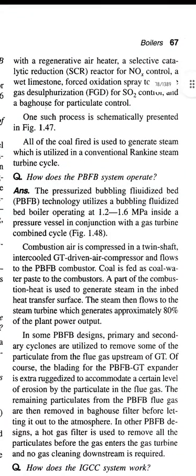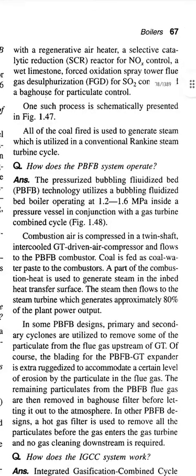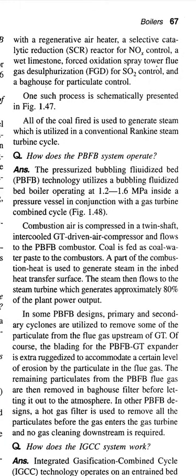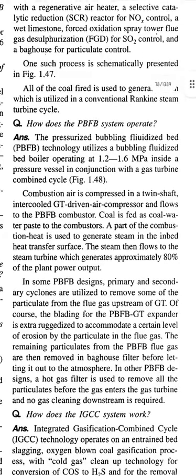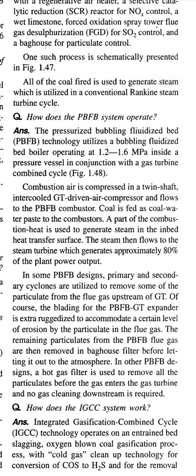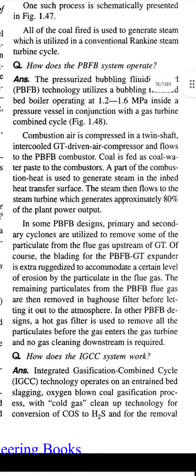How does the PBFB system operate? The pressurized bubbling fluidized bed technology utilizes a bubbling fluidized bed boiler operating at 1.2 to 1.6 MPa inside a pressure vessel, in conjunction with a gas turbine combined cycle. Combustion air is compressed in a twin-shaft intercooled gas turbine-driven air compressor and flows to the PBFB boiler combustor.